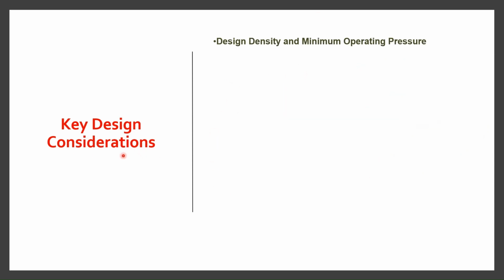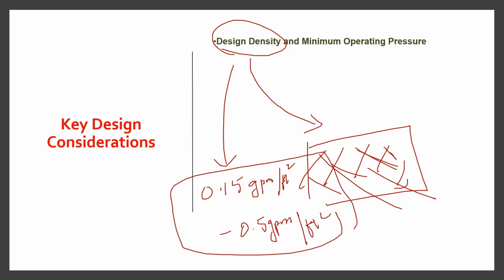Next key design consideration is design density and minimum operating pressure. It's not as simple as spraying water everywhere in order to protect the equipment or cool the surface. Design density is one of the most important consideration in water spray system. So as per NFPA 15, the design density can range from 0.15 GPM per square feet to 0.5 GPM per square feet. For each and every equipment, there is a fixed design density. We will cover that in next slides.